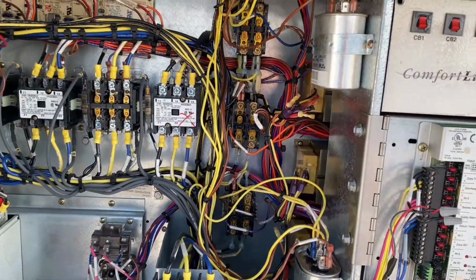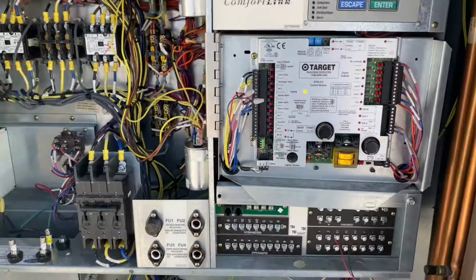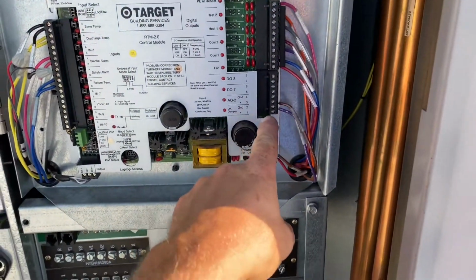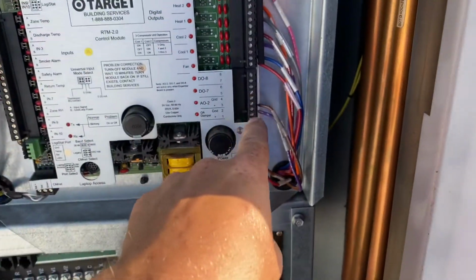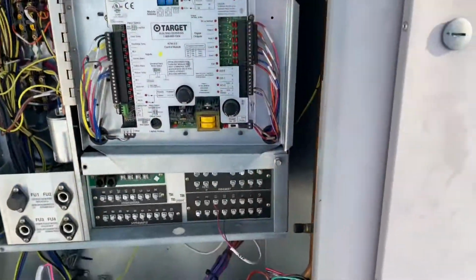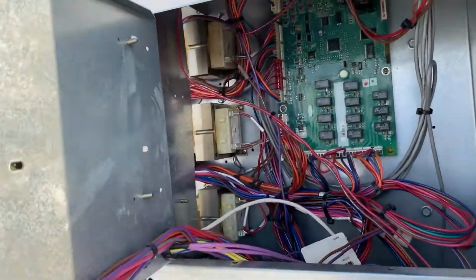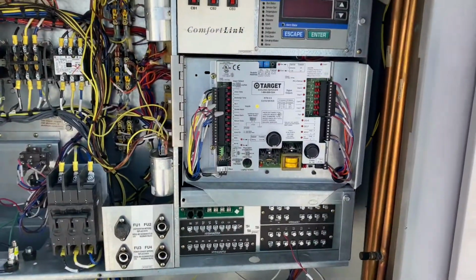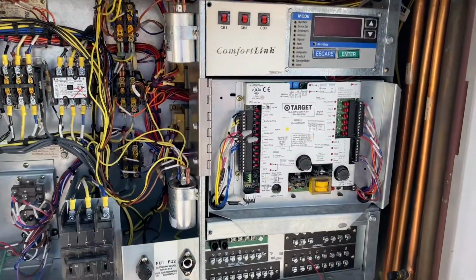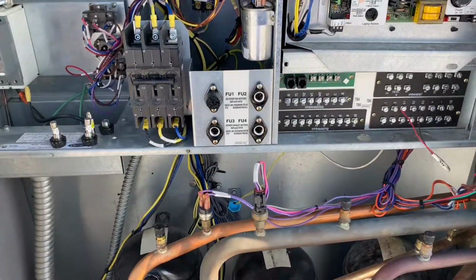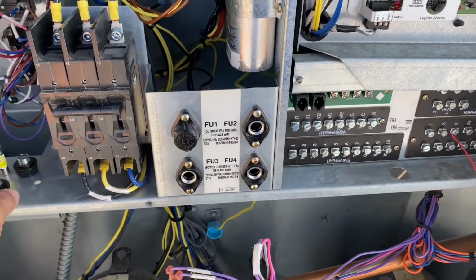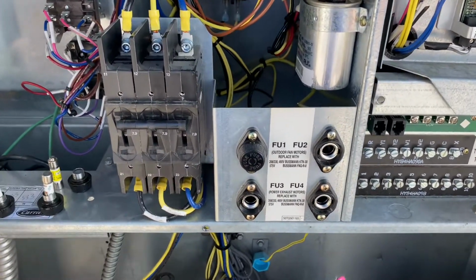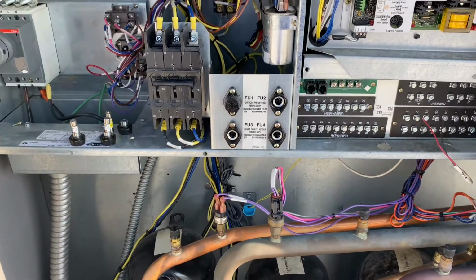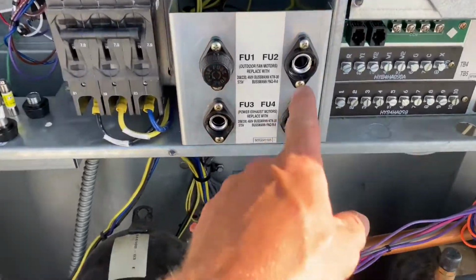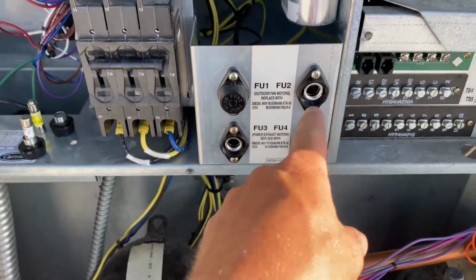so I read voltage on the transformers. And well, first I read voltage on this main board right here, the communication board. Didn't have 24 volts coming in. So behind here are all the transformers, and didn't have 24 volts coming out of them either, or any of them, all 3. So then I went down to these low 30 amp fuse blocks, and checked them one by one. And these 3 are bad. This one's good. These 3 are bad.